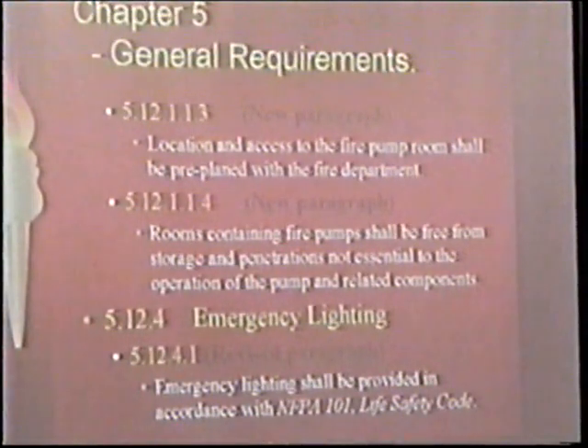The key point, I guess one of the key ones, is we just did a job down in St. Paul. It's in a converted building, converted to condos. You get in the fire pump room and you've got an aisleway that's almost 3 feet wide, and it's about 15 feet back to the controller. The controller is mounted backside to you, freestanding in the room. So you have to go down that aisle, past the boilers, around the fire pump controller to turn it on. Probably not what you want to be doing in an emergency.